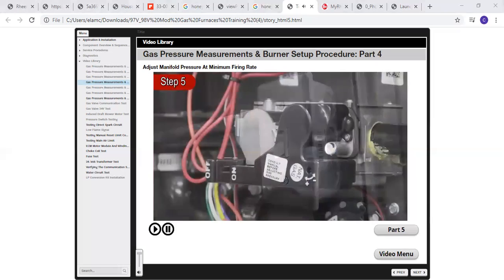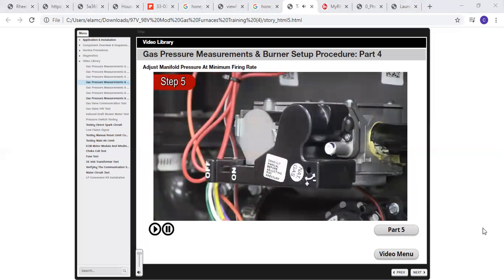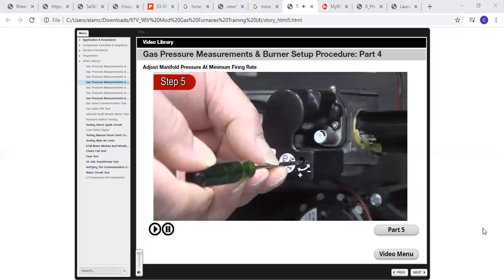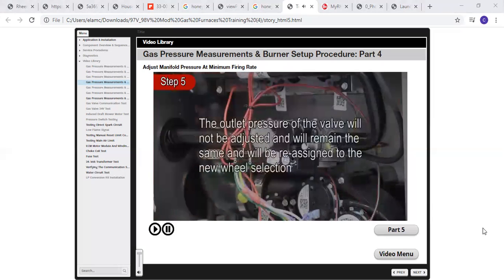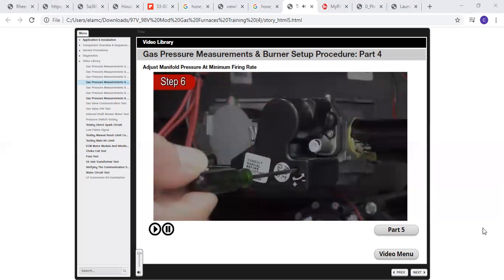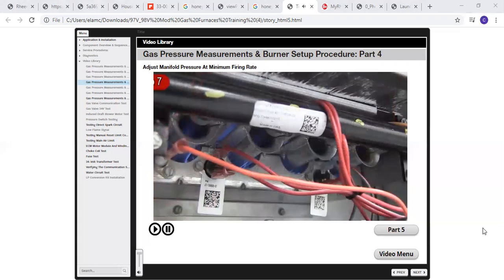If power to the furnace, and therefore the gas valve, has been interrupted and the adjustment wheel turned while power is off, the outlet pressure of the valve will not be adjusted and will remain the same and will be reassigned to the new wheel selection. Step 6. Repeat steps 4 and 5 if necessary.